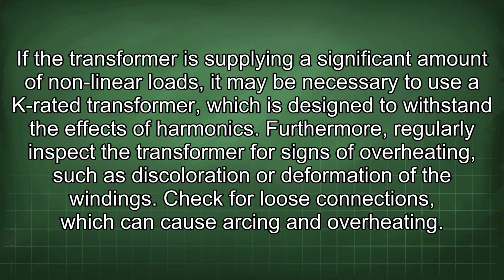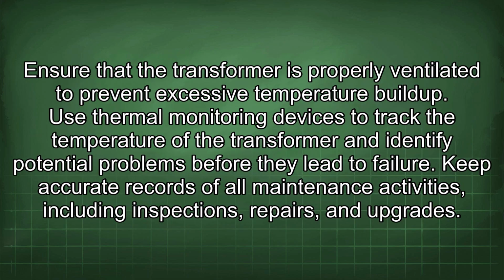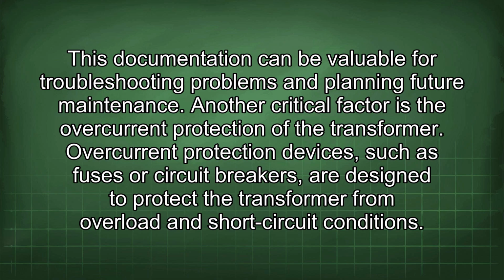Furthermore, regularly inspect the transformer for signs of overheating, such as discoloration or deformation of the windings. Check for loose connections, which can cause arcing and overheating. Ensure that the transformer is properly ventilated to prevent excessive temperature buildup. Use thermal monitoring devices to track the temperature of the transformer and identify potential problems before they lead to failure. Keep accurate records of all maintenance activities, including inspections, repairs, and upgrades. This documentation can be valuable for troubleshooting problems and planning future maintenance.